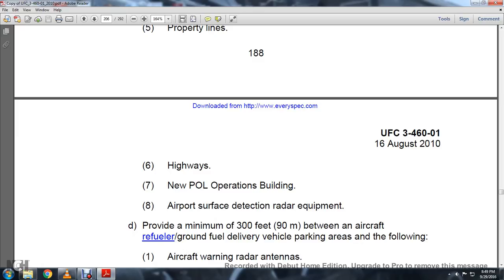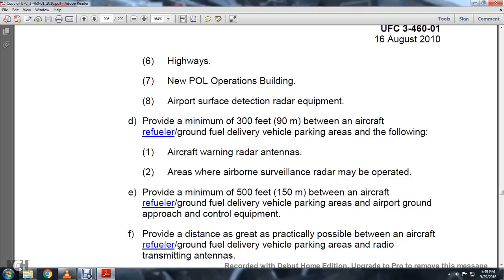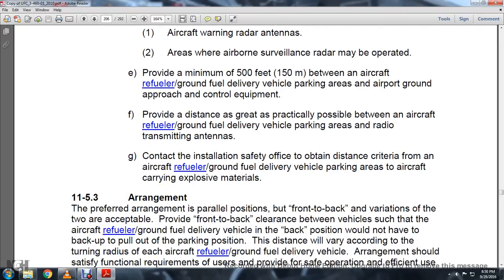Provide a minimum of 300 feet between the aircraft refueler or ground delivery parking and the following: aircraft warning radar antennas and airborne surveillance radar that may be operated. Provide a minimum of 500 feet between the aircraft and the refueler or ground fuel delivery parking areas and the airport ground control equipment. Provide a distance as great as practicably possible between the aircraft refueler or ground fuel delivery vehicle parking areas and radio transmitting antennas. Contact the installation safety office to obtain design criteria for the aircraft, refueler, ground fuel delivery vehicle, and parking areas near aircraft carrying explosive materials.